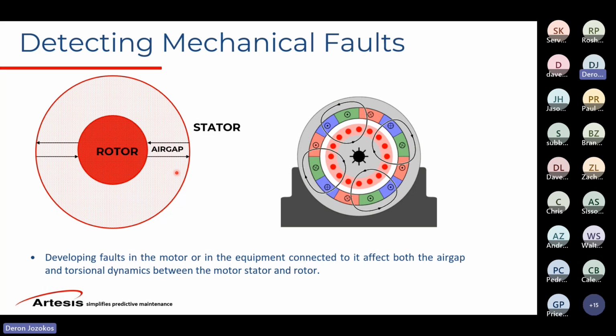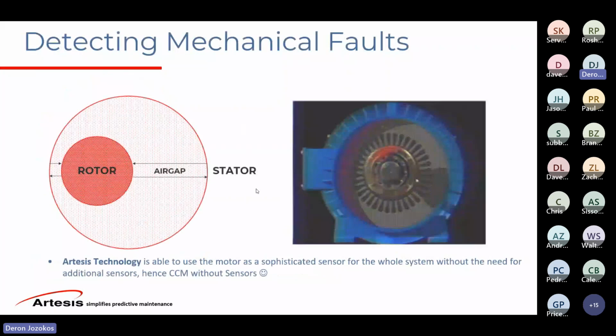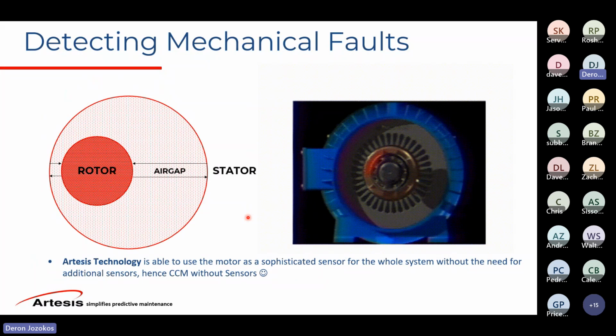The electromagnetic forces between the rotor and the stator, is where we're listening to all of the machinery and the components in the whole machine train. So if you have a misalignment, you're going to have some eccentricities and some vibration between the rotor stator. If you have a bad bearing on the fan, even through the belts or gearbox or what have you, it's going to hear the whole thing. So for those vibration folks out there, just think of this air gap as a very sensitive accelerometer in every direction, listening to the whole machine train. So even through the belts, through gearbox, it's going to see all of those.